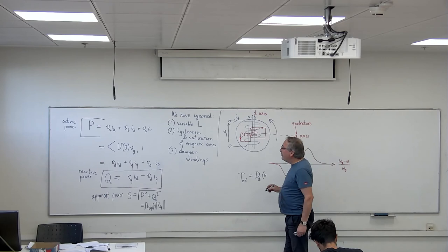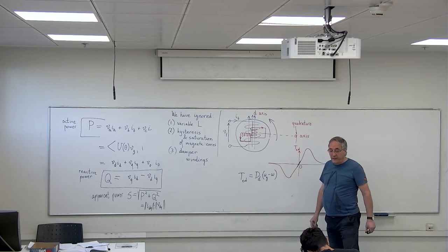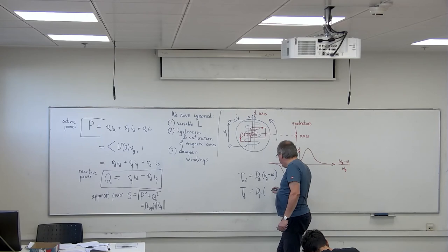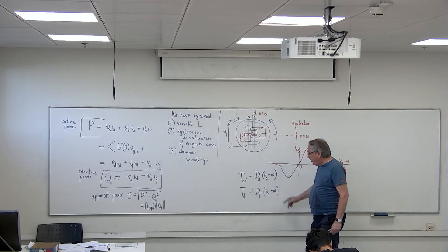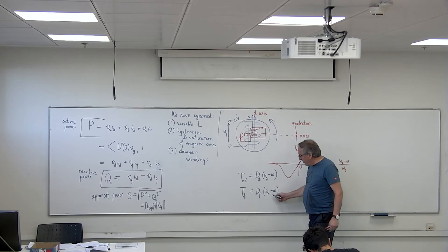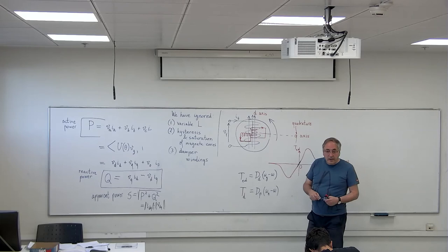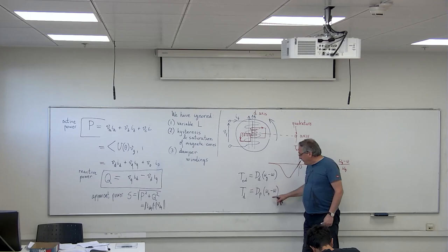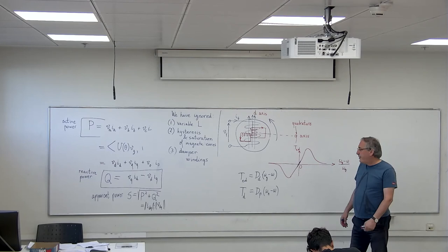omega, the local frequency. Remember what was the droop torque? The droop torque was dP times omega nominal minus omega. So you see, it's very similar. But here we compare to the nominal frequency, and here we compare to the actual grid frequency. So both of these torques are pushing the machine towards the desired frequency. One pushes towards the nominal frequency, the other pushes towards the grid frequency, and both of them have a very strong stabilizing effect on the machine.